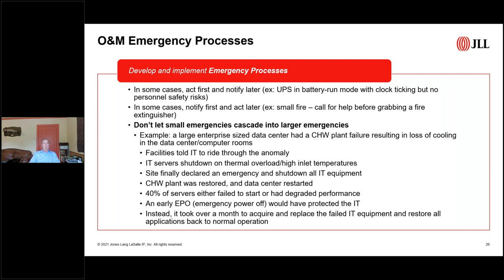An example that I know of was a site with a large critical data center for a large healthcare organization. They had a chiller plant failure. All of the chillers stopped working, and the data center was at risk of overheating without cooling. The facilities team told the IT group that they could resolve it and to keep running. Don't shut down, we're going to fix it. They didn't get it fixed in time.